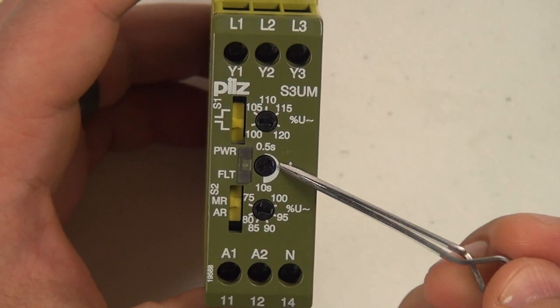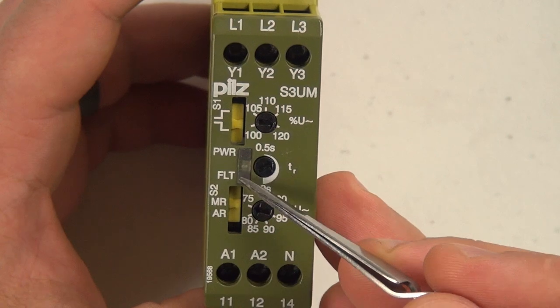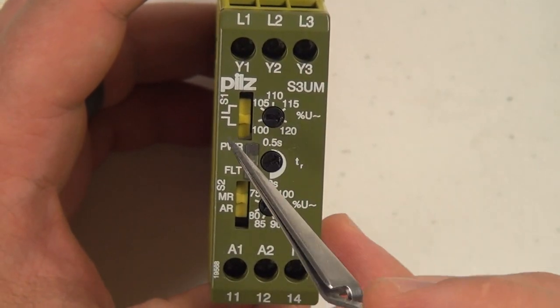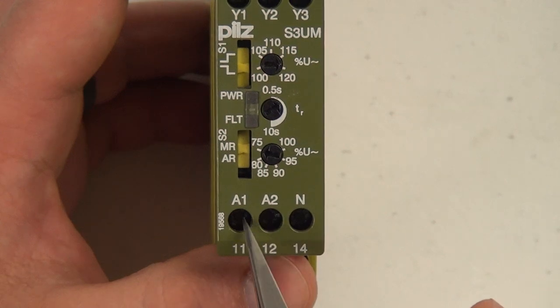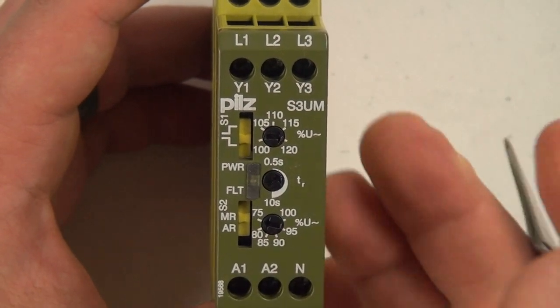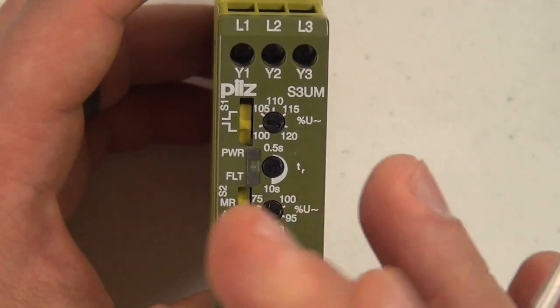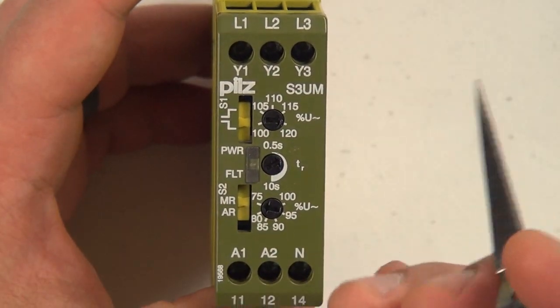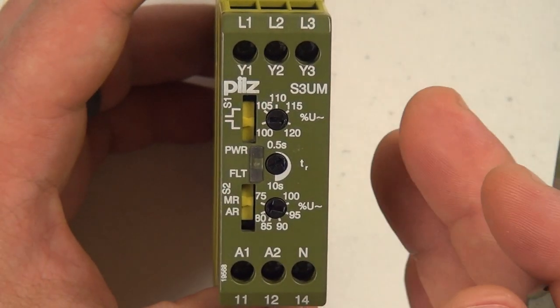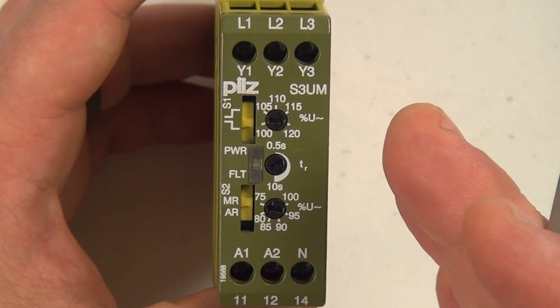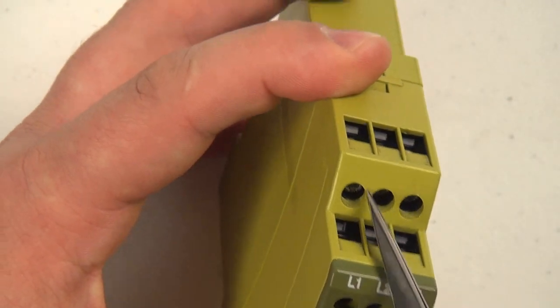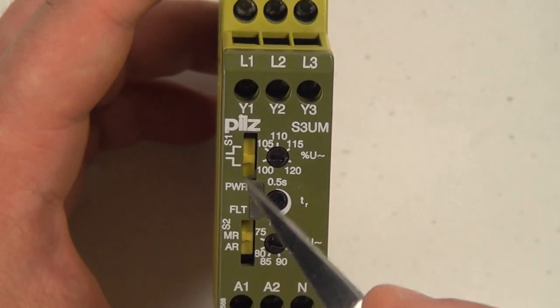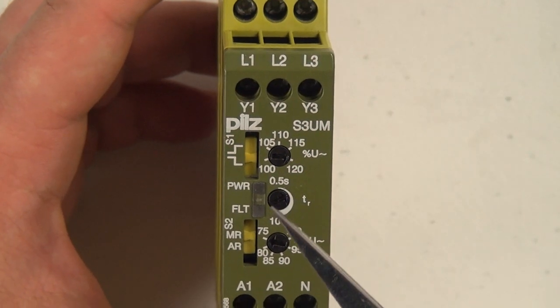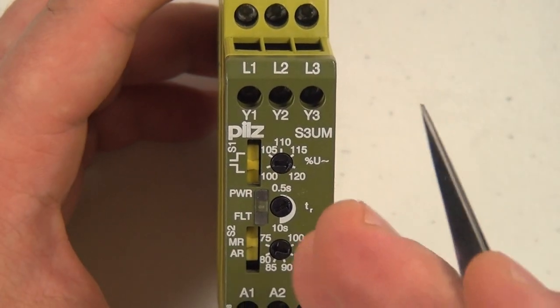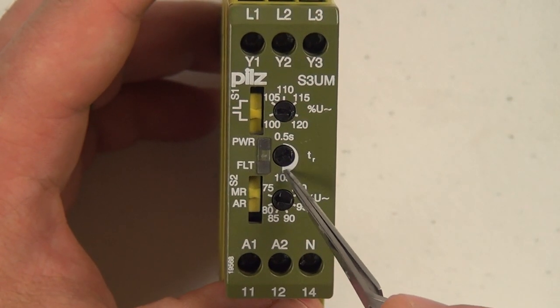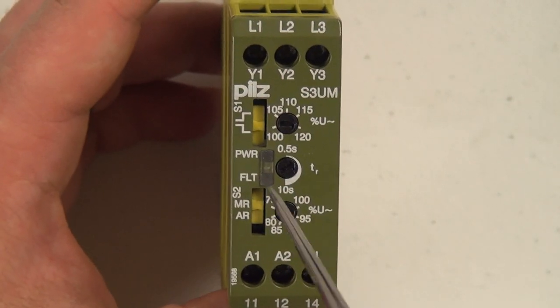What I absolutely hate about this relay is that it has two lights. It has power, which, okay, whatever, we know that you're powered, meaning you have 24 volts sitting here, and you have fault. The single fault light is the stupidest thing on the face of this planet, because from this one light, you know the relay's faulted, but why? Are we missing a phase? Do we have an asymmetry problem? Is the voltage too low? Is the voltage too high? There are so many questions that you can't answer just off of one light that says I'm faulted. Something's wrong. Blah, blah, blah.